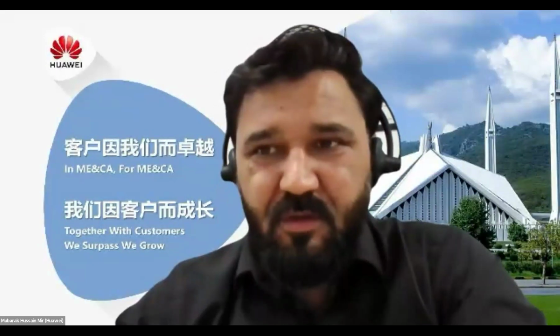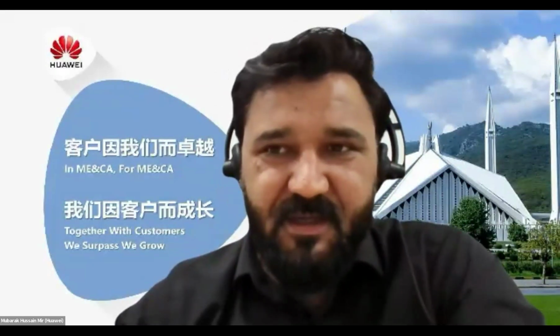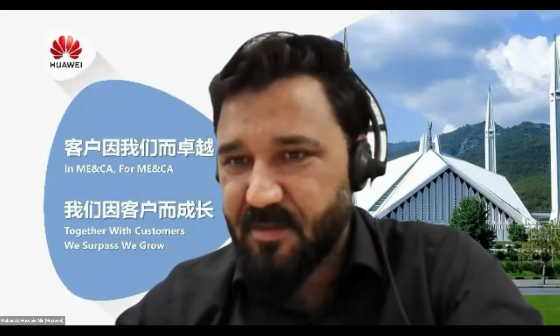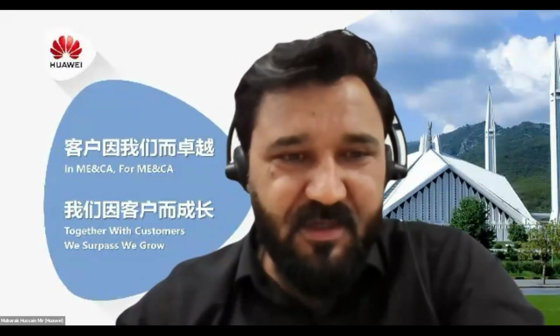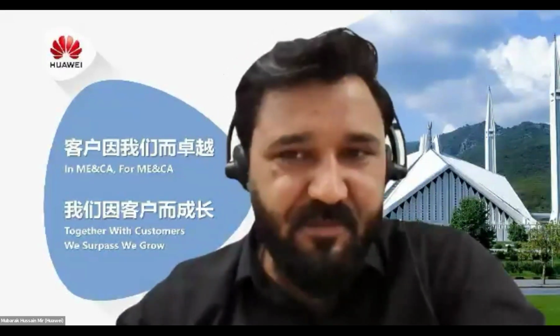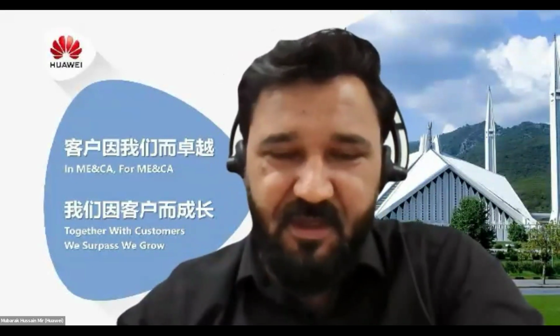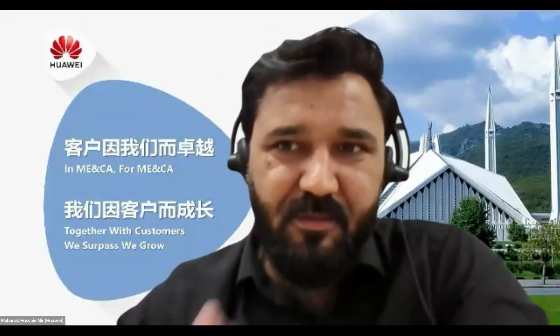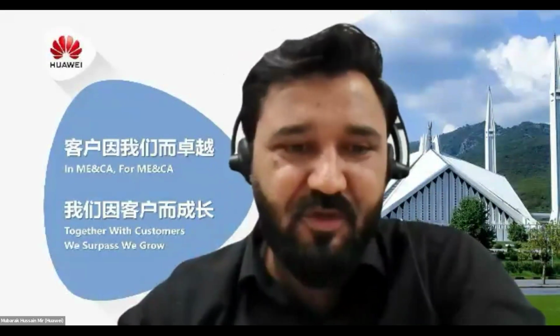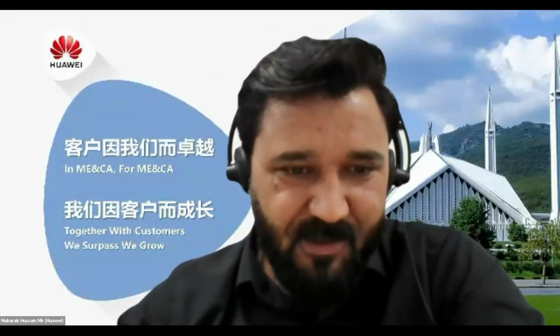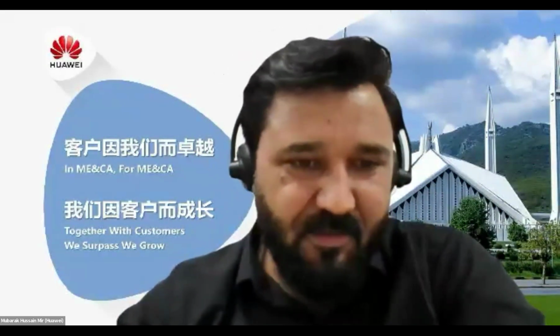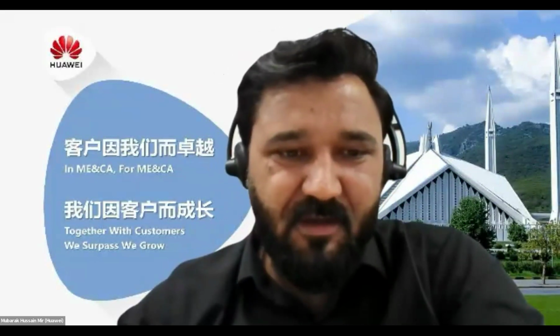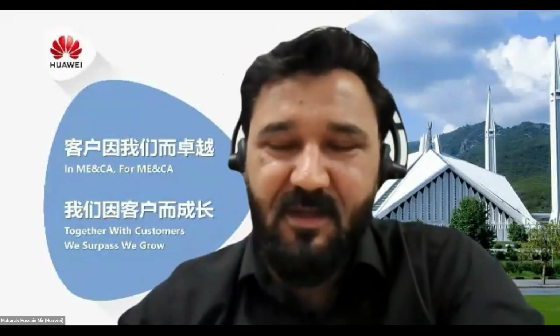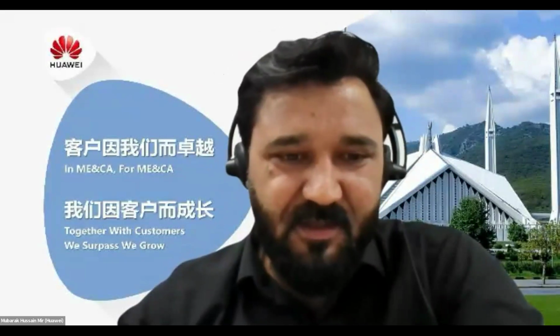I don't think so. Especially, many times we've told in our seminars, if the protection is built in from the Huawei side, from our inverter, it is mentioned and available there. You don't need to put the protection. A lot of people even ask us whether we should put the DC breaker before the inverter or not. We strongly do not recommend it because the protection is already available there. The disconnect switch is there. The DC safety feature is built into the inverter.